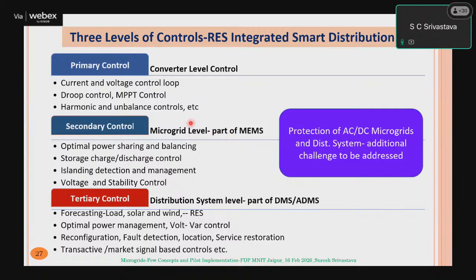But at the microgrid level, because you will have more than one source and you may have storage, how do you balance the power between them to meet the load demand? And if you are connected to the grid, how are these three or four being balanced? That is part of the energy management system. For storage charge and discharge, you have to decide when to charge, when to discharge, and how much it should be charged. It should not fall below 20% of the state of charge, and it should not go above 90%, to avoid sacrificing its life. Then how to detect islanding, how to manage the islanding, and how to reconnect with the grid, that control should also be there, along with local voltage and stability control. This is called secondary control and becomes part of the microgrid energy system.